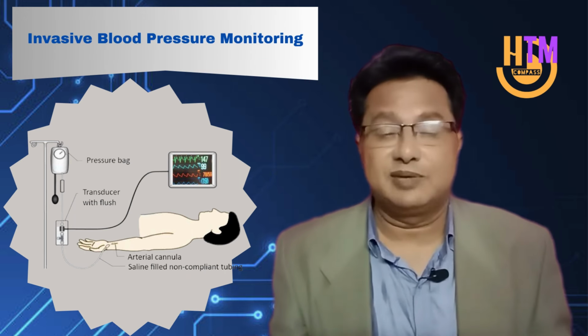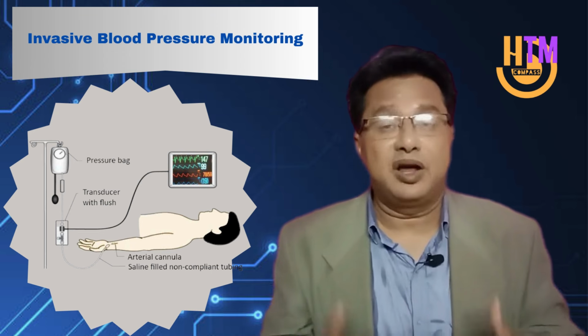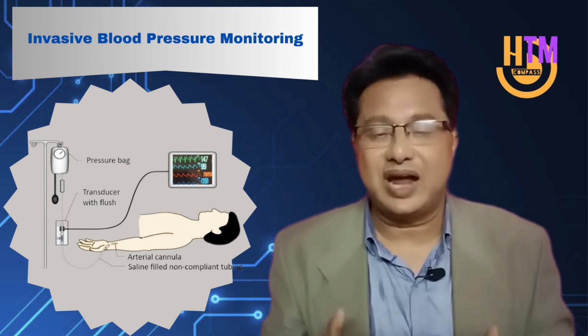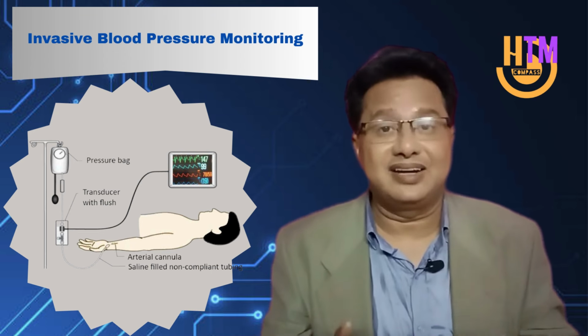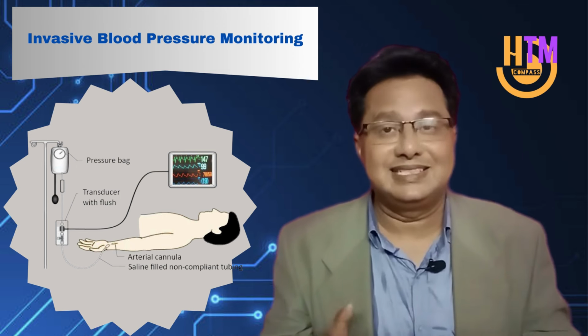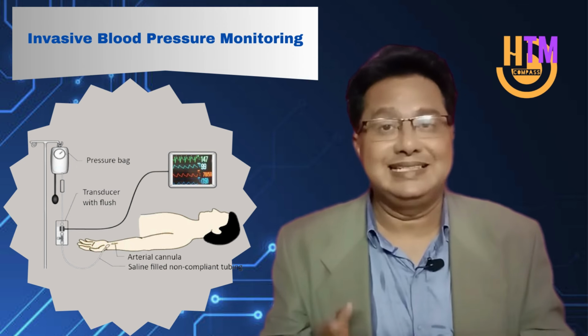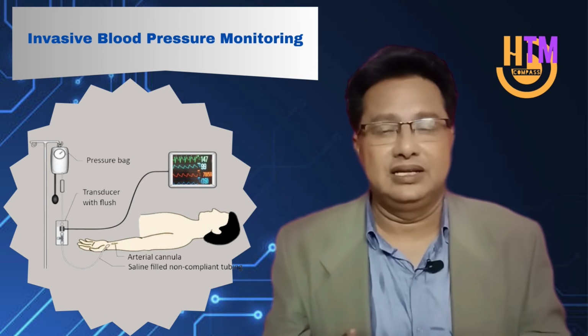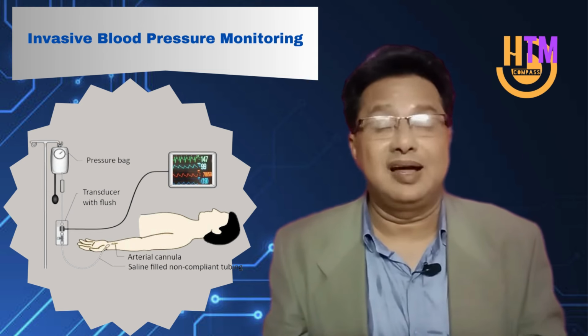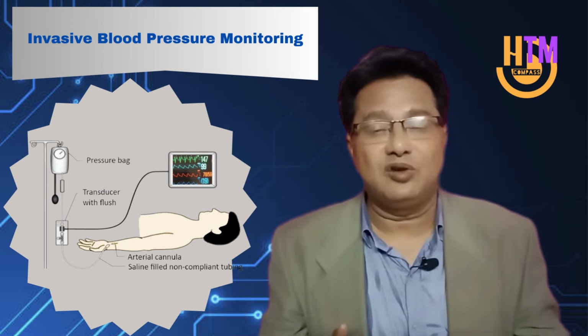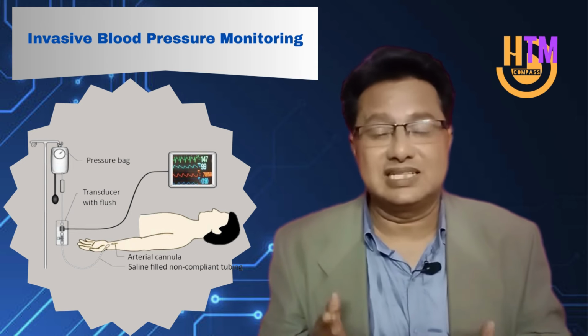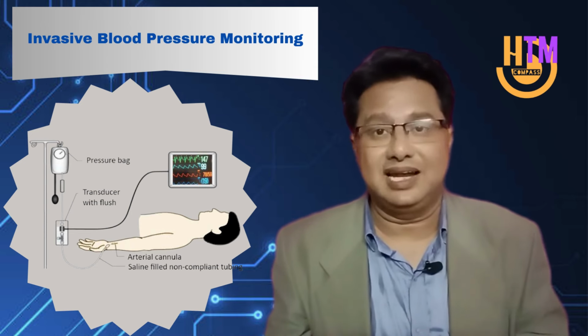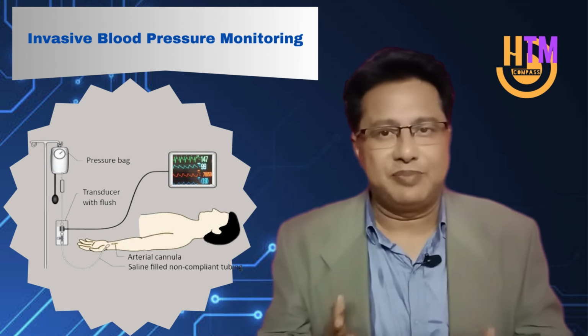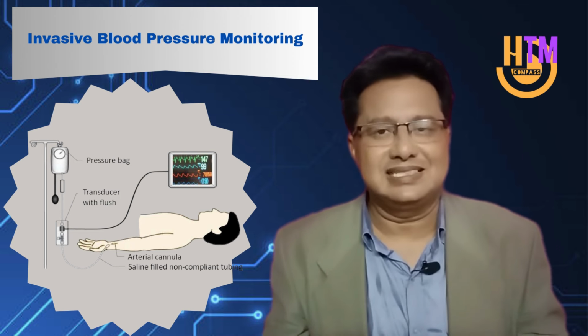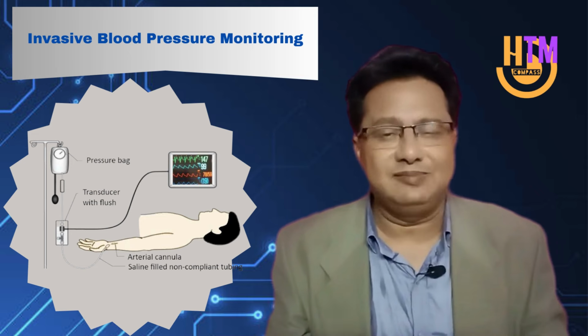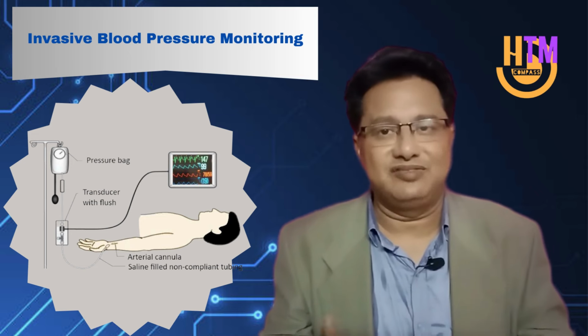Invasive blood pressure monitoring is the procedure that monitors the arterial pressure by directly interacting with the blood in the artery, and that artery is the radial artery. That is done through a cannula needle that is inserted through the skin to the artery via palpation or with the help of ultrasound imaging. The other end of the cannula is connected to a fluid-filled system, and that fluid-filled system is further connected to a pressure transducer. That pressure transducer converts pressure into an electrical signal, and with the help of some algorithm, it shows the arterial pressure on the physiological monitor.